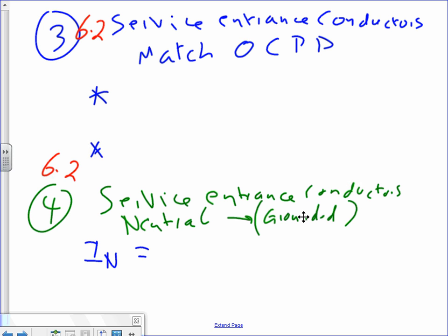Now, service entrance conductors, guys, typically we match the overcurrent device. Match the overcurrent device. Okay, so I have 1600. Now, do me a favor. Can you guys go to table 310.15(B)(16) and find yourself a 1600 amp? Brandon, do they have 1600 amp? Look at the 75 degree column. Oops. What would you do? 310.15(B)(16). Okay. Did anybody find a cable that can carry 1600 amps?